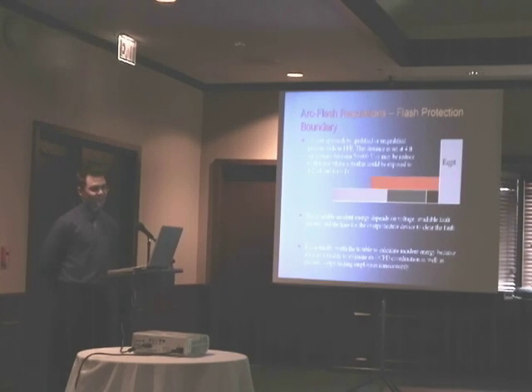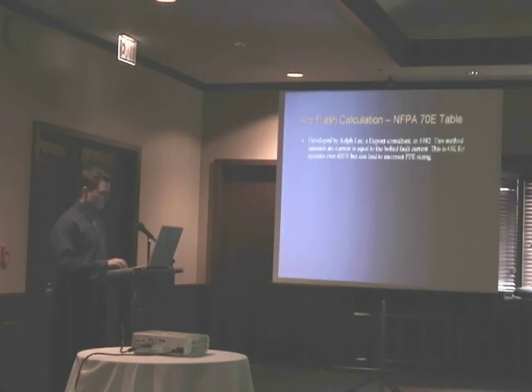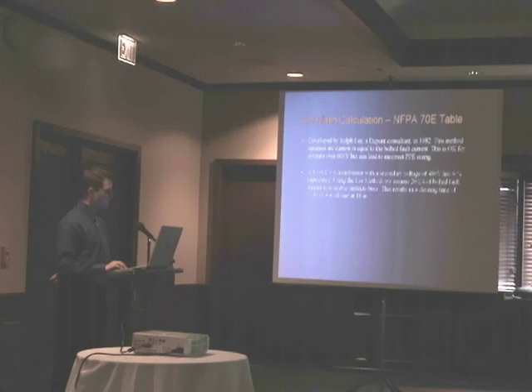protecting employees unnecessarily. You don't want to have too much equipment on that could get in your way if you don't need to have it on to be protected. Okay, now the arc flash calculation, this is from the NFPA 70E table. It's developed by Ralph Lee, a DuPont consultant in 1982. This method assumes arc current is equal to the bolted fault current. This is okay for systems over 600 volts, but can lead to incorrect PPE sizing.